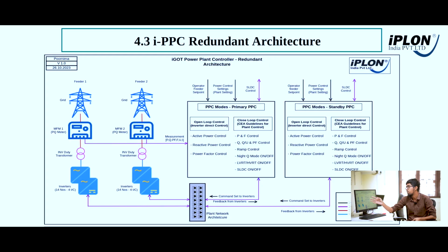This is the iPLON architecture diagram. I previously explained that we have closed loop control, where we get feedback from the PQ meter. In the site, inverters are connected to the transformer, which is connected to the grid. Depending on the site, the number of feeders will vary. We take two feeders as the example. This is the iPLON redundant architecture.